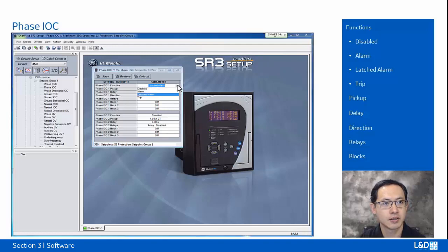If the function is set to Trip, that means it will operate the trip relay, that's output relay number 1, and also other selected auxiliary relays, and also turn on the trip LED on the front panel. The pickup level setting selects how much current is needed to operate the Phase IOC pickup.